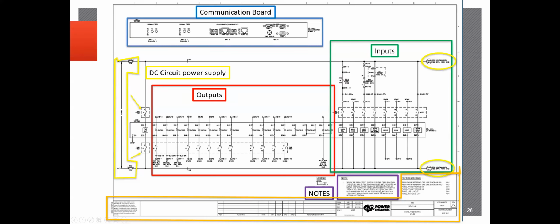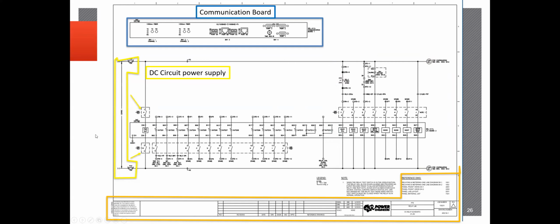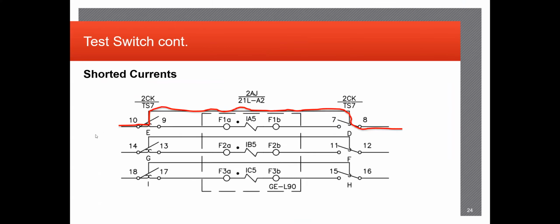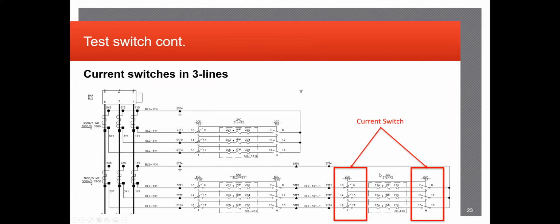A lot of times we inform everyone that they need to verify the relay test switches correctly correlate, not only on the prints, but in the station itself, that everything matches up correctly. For instance, going back to one thing that I'd like to mention, I mentioned the shorting blocks and putting credit cards, paper in those to break the circuit. Well, the reason for that is because if you don't do that and you open these switches, this whole circuit's still going to be made up.